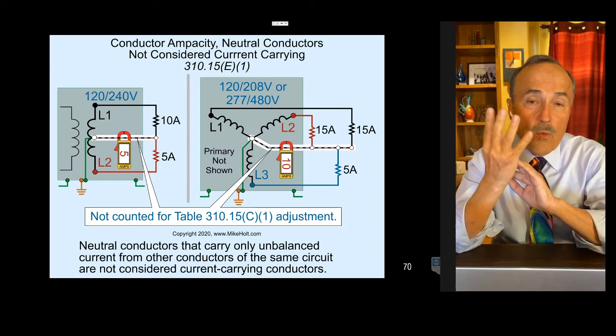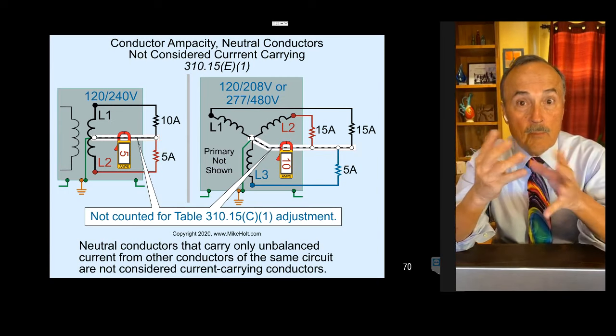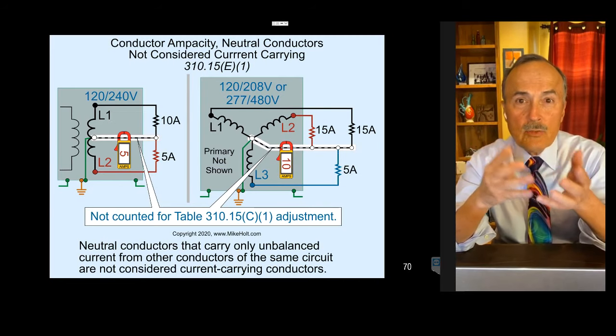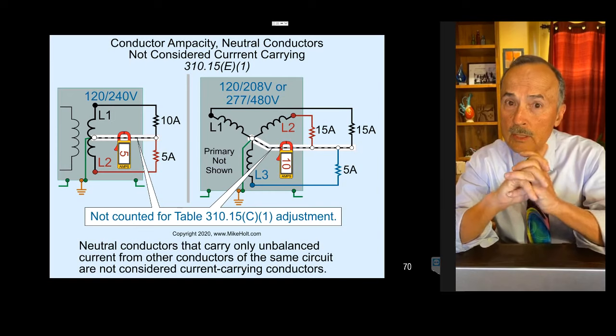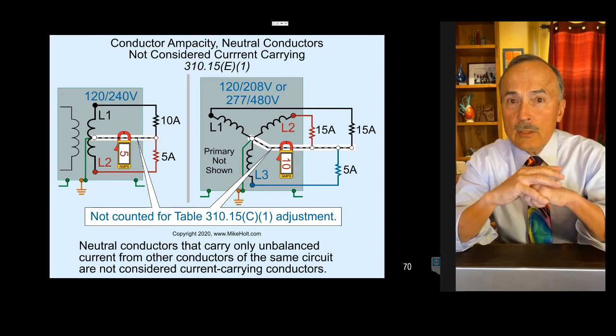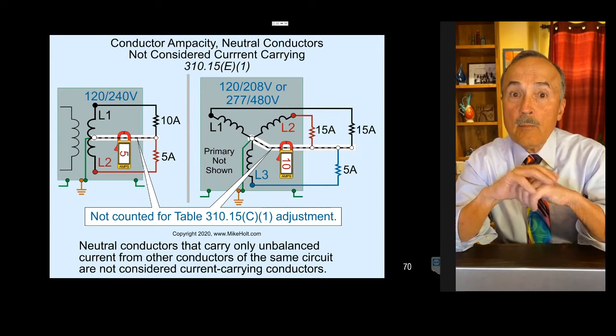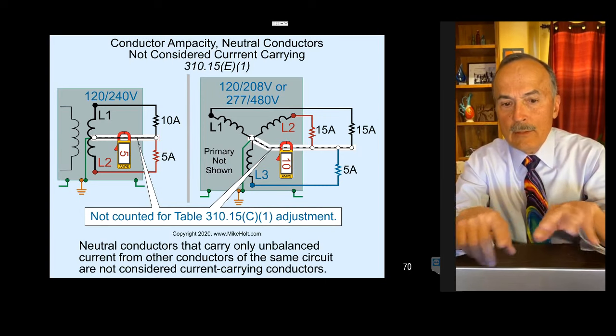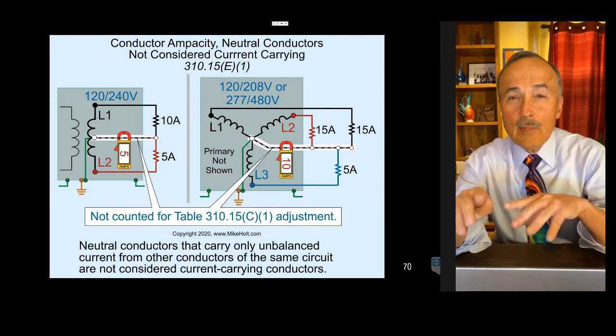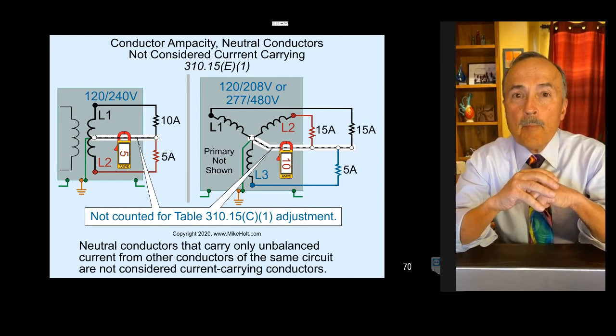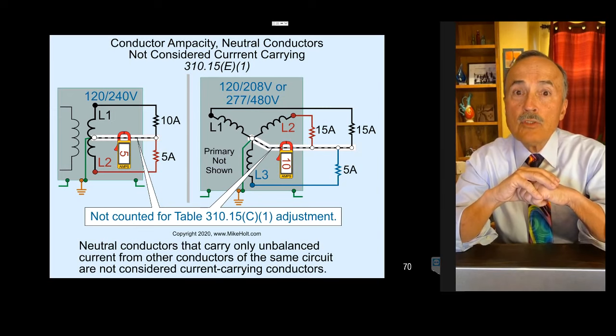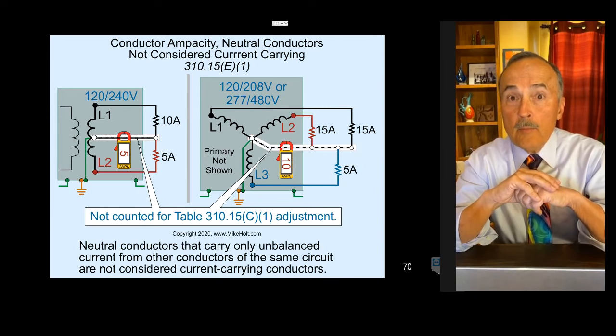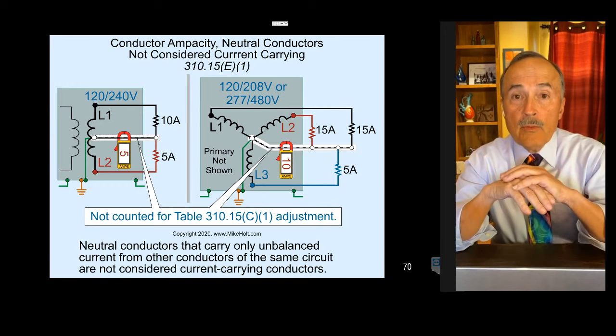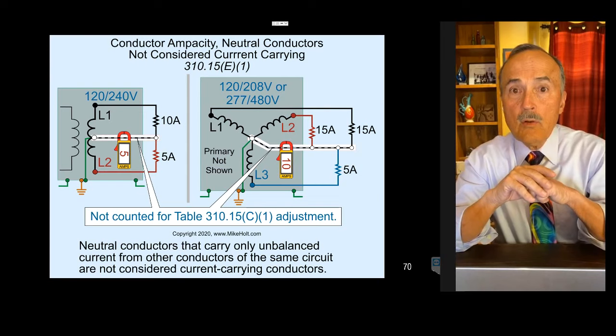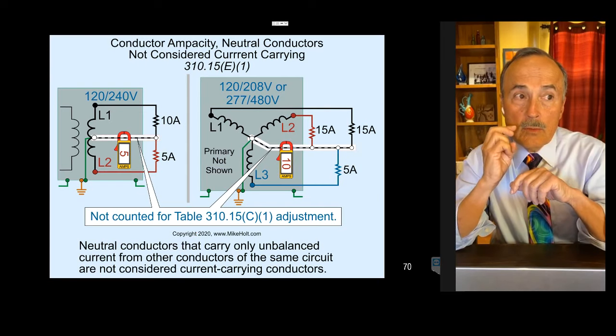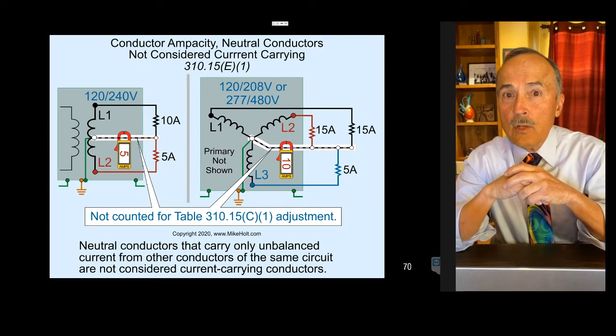Okay, I mentioned yesterday that a neutral conductor, if it's a 2-wire circuit, well then hot current goes out, current comes back. Well, the neutral will be a current carrying conductor. But if it's a 3-wire or a 4-wire multi-wire branch circuit, meaning 2 hots and a neutral, 3 hots and a neutral, we talked about multi-wire branch circuits yesterday, that neutral conductor is not considered a current carrying conductor unless, we're not going to get into the rule there, it's right there in 310.15E, it's probably 2, maybe 3, unless that neutral conductor carries a major portion of the load nonlinear.